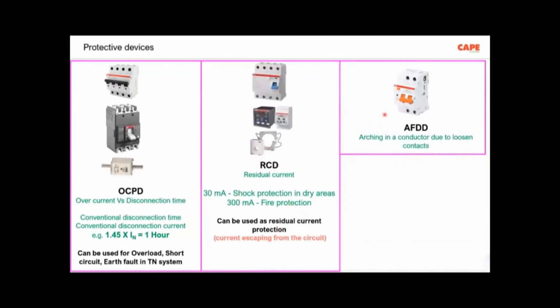The third kind of protective device is called AFDD, arc fault detection device. These devices are used to protect a circuit from loose contacts. Let us say you have a phase conductor with a loose contact, and due to arcing, probably over a period of time it can ignite fire. But this AFDD protects that particular circuit from arcs. So arcing in a conductor due to loosened contacts can be detected with AFDD, but don't think that arcing at a loose contact in an earth wire will create a tripping, because the earthing is not considered here. Only the line and neutral in case of a single phase circuit. If there is a loose contact, this device will trip.